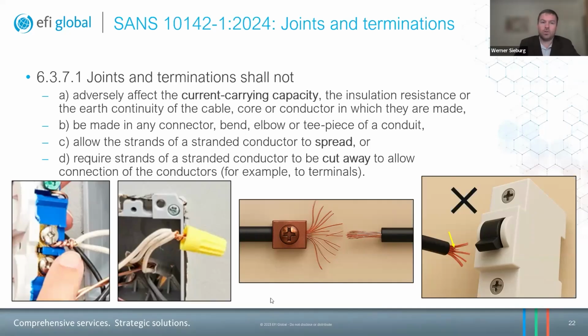And my caution in that regard would be, a conductor is sized for a certain current, and it needs to be of that gauge all the way through into the terminal, not just up to the terminal. If you cut certain strands away, that will take away the current carrying capacity of the conductor in that area, and may also result in a hotspot and a fire. Yes, and that's all from my side.